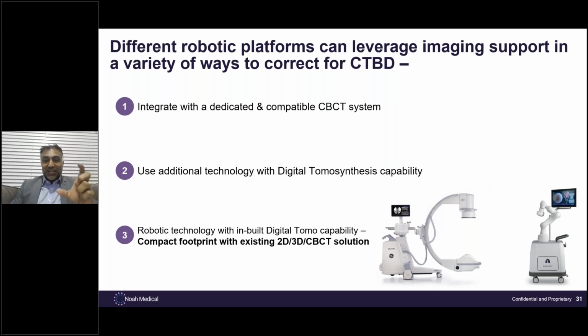And as a result, you take 2D images, which you would normally see with a regular fluoroscopic image, and develop a 3D image by stacking them over one another and changing the density so you identify that image. As a result, when you've identified where that nodule is in real time, compared to where it was when the CT was done, in the setting of changes in ventilation and chest wall rigidity with anesthesia, you make up for that CT to body divergence. And that's really what you're doing with the Galaxy. You're integrating the imaging into the robotics.